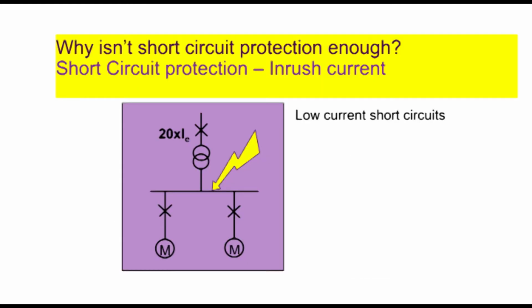Why is short circuit protection not enough? There are a lot of applications that require selective protection, where you have upstream and downstream breakers tripping. Generally, you'd like to isolate the fault, and you'd like the breaker closest to the fault to trip. In cases like this, where you have to set different levels of current and different time delays, you may have to set your upstream or main circuit breaker at, for example, 70 milliseconds. That may not be enough to trip your breaker in the event of an arc fault. That is the reason why you should have an arc guard system.